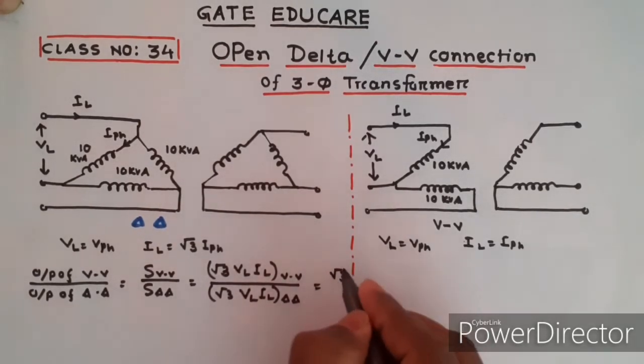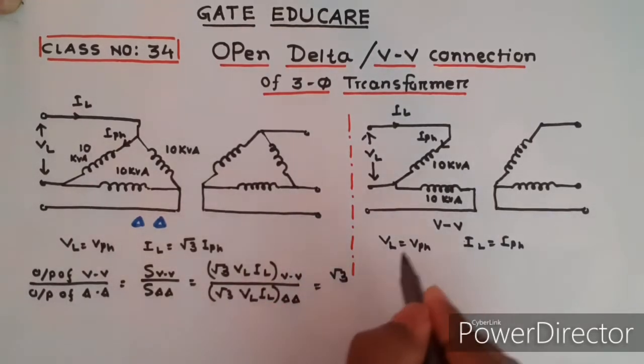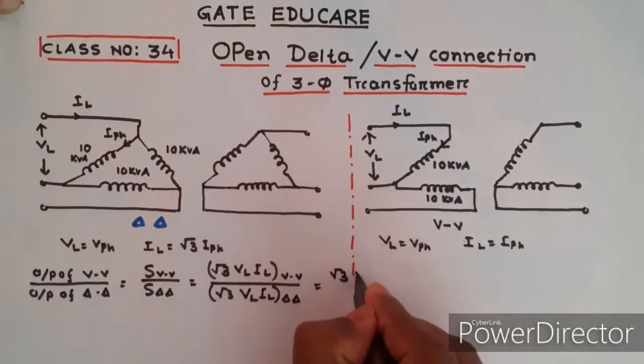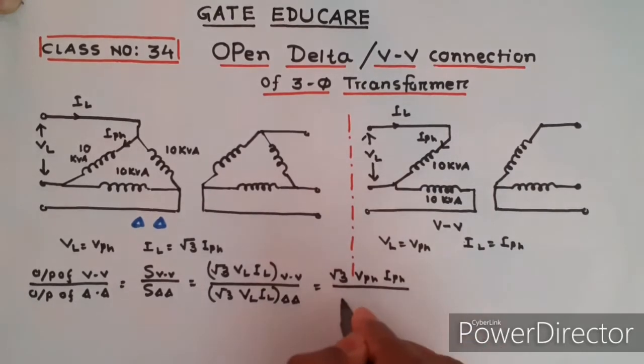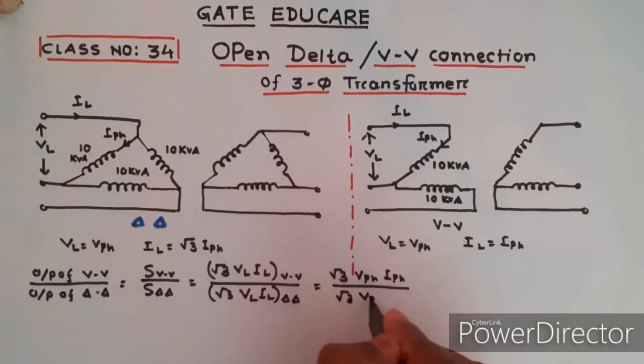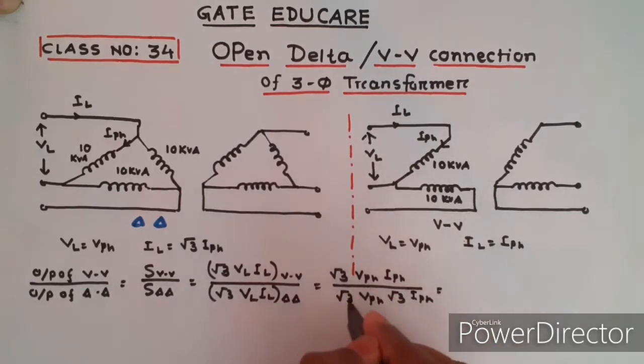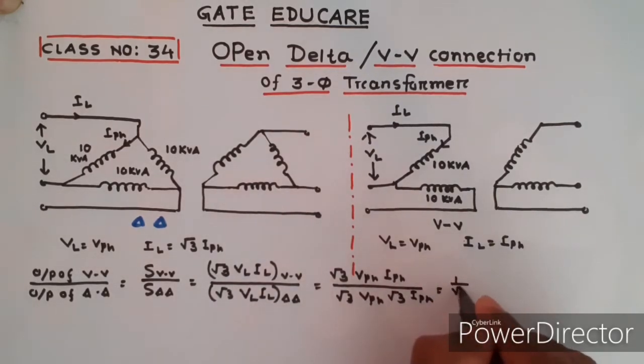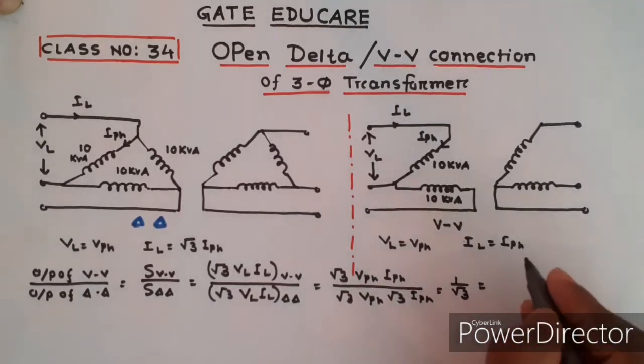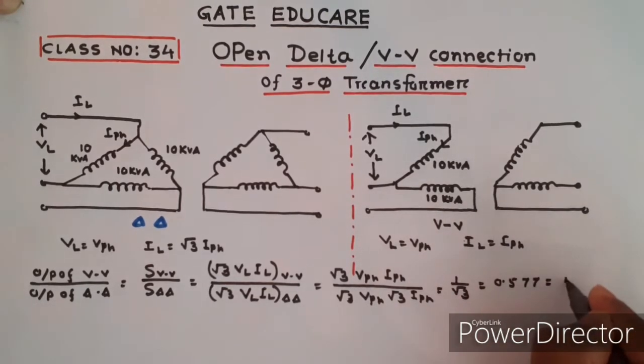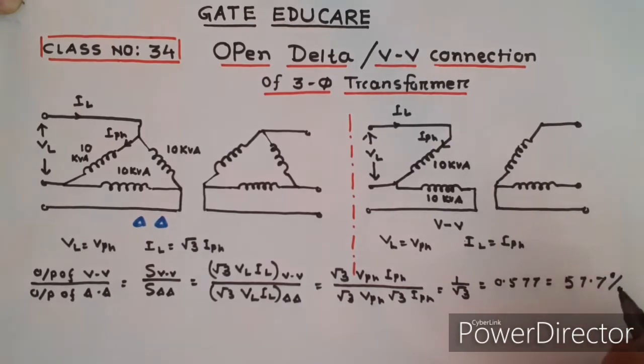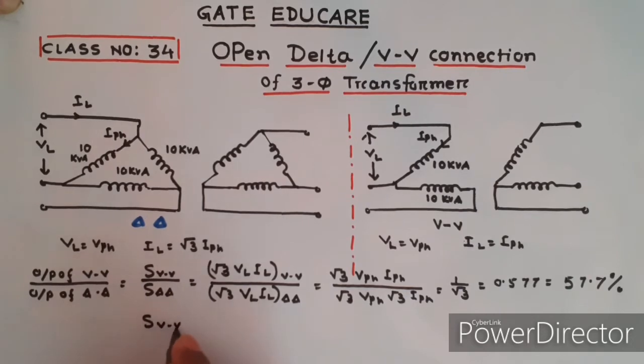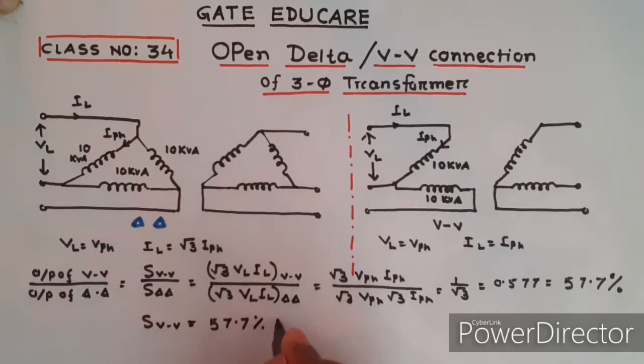In the V-V connection, VL equals V-phase and IL equals I-phase, so the numerator becomes V-phase times I-phase. In the delta-delta connection, VL equals V-phase and IL equals root 3 times I-phase. The root 3 terms cancel, V-phase cancels, and I-phase cancels, giving 1 over root 3, which equals 0.577 — that is 57.7 percent. This means the rating of the V-V connection is 57.7 percent of the delta-delta output.